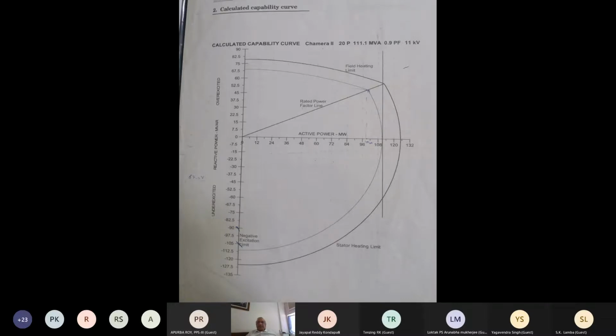So if you are operating the excitation system in manual mode, you can still refer to the capability chart so that you don't exceed the field current limit on the exciter, to take care of its thermal capability. In the under-excited mode also, the characteristic is more limited by the overheating in the end region rather than the current limit, because you are actually absorbing the reactive power from the grid. So there is a reduced requirement of the field current in the under-excited mode, because you are drawing excitation from the grid, thereby taking reactive power from the grid. So the limitation comes more because of the overheating rather than the current limit.